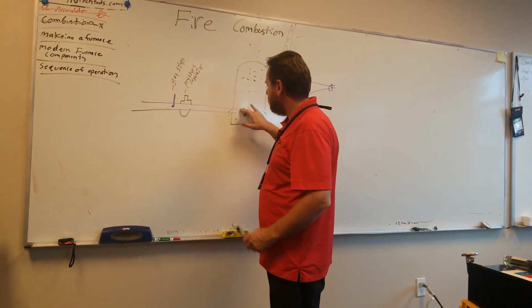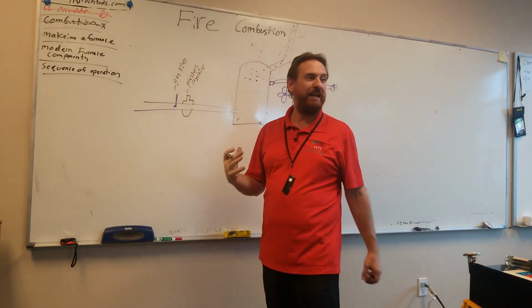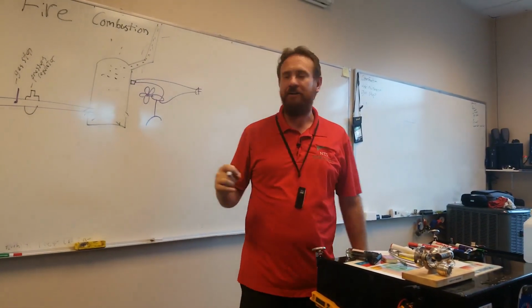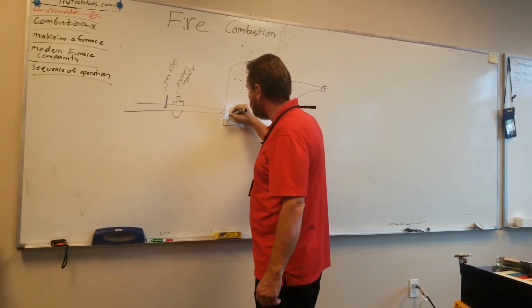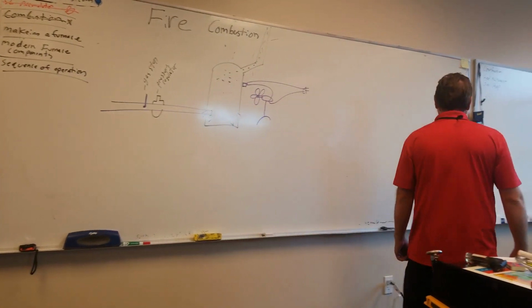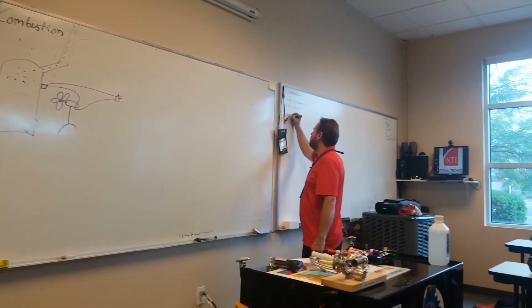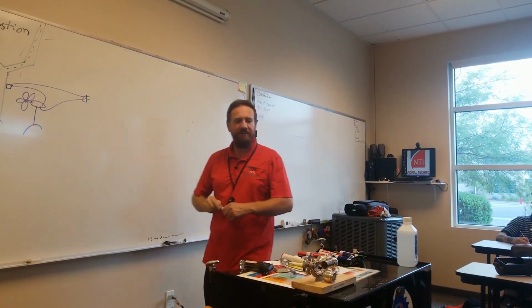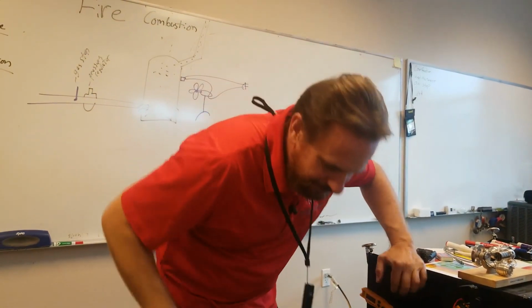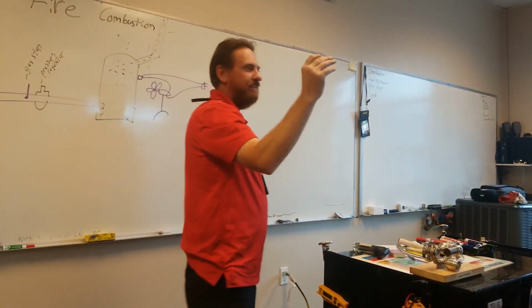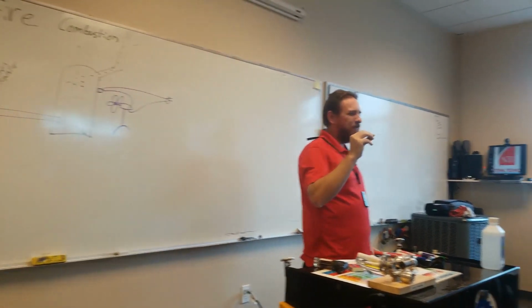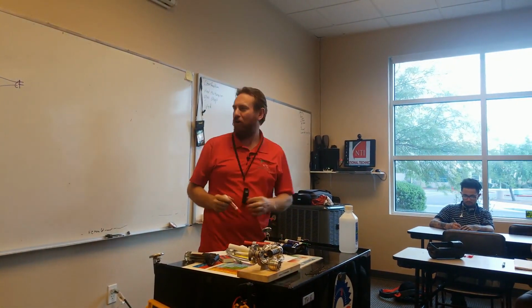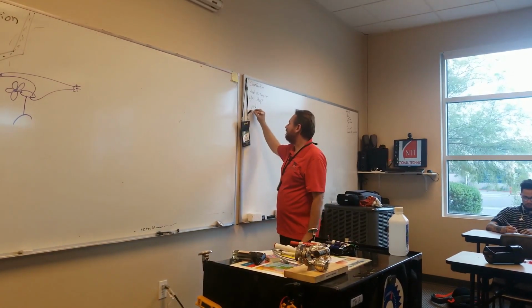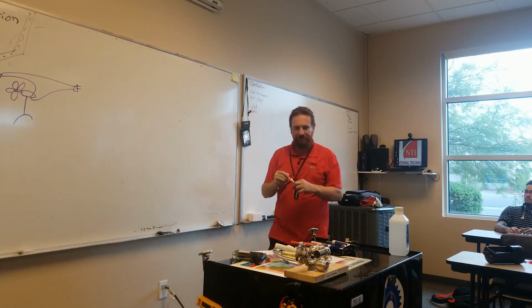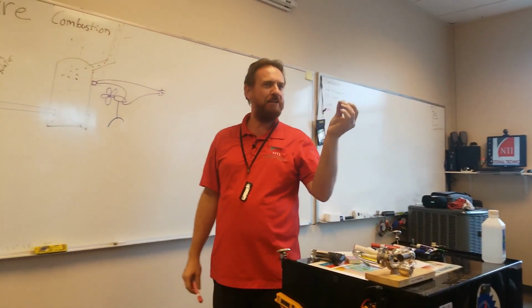The other thing I'm going to do is on the very end of this pipe, that pipe is just too giant, it's too big. I need to have a smaller amount coming out. So what I'm going to do is thread a fitting on the end of that. And that fitting I'm going to thread on the end of it is called a spud. Like a potato, spud. This is a spud. Inside of the spud, what we have is a hole drilled in it. That hole that's drilled in the spud is called an orifice. So this is a spud with a hole drilled in it.